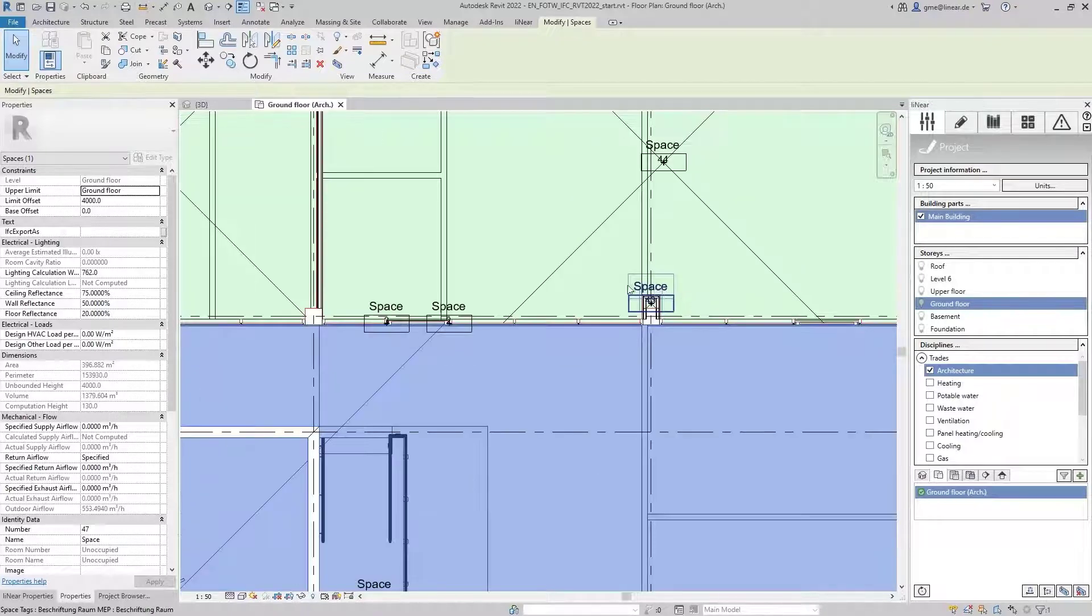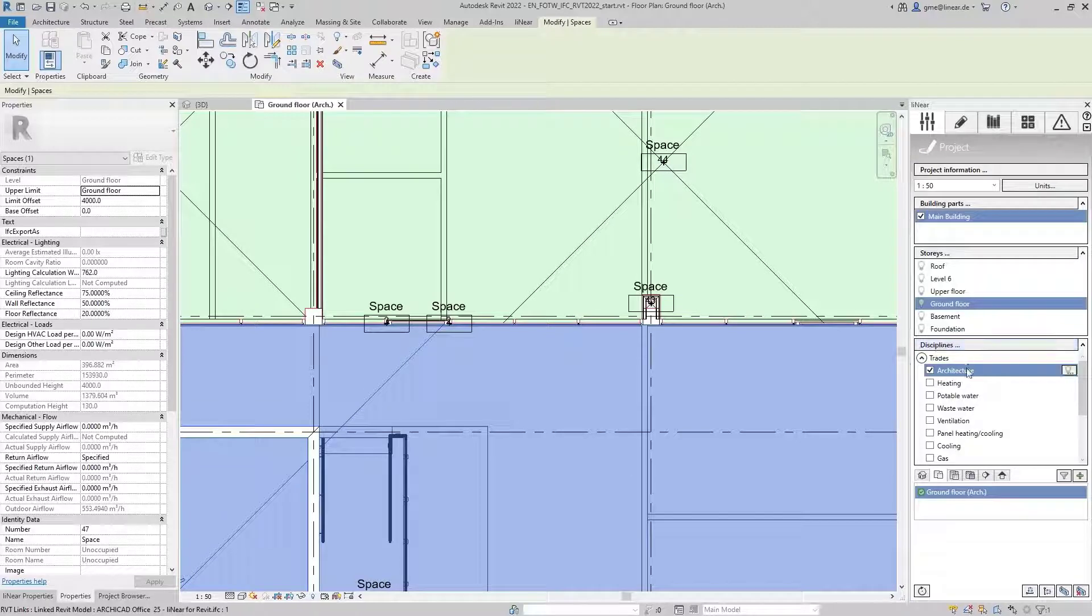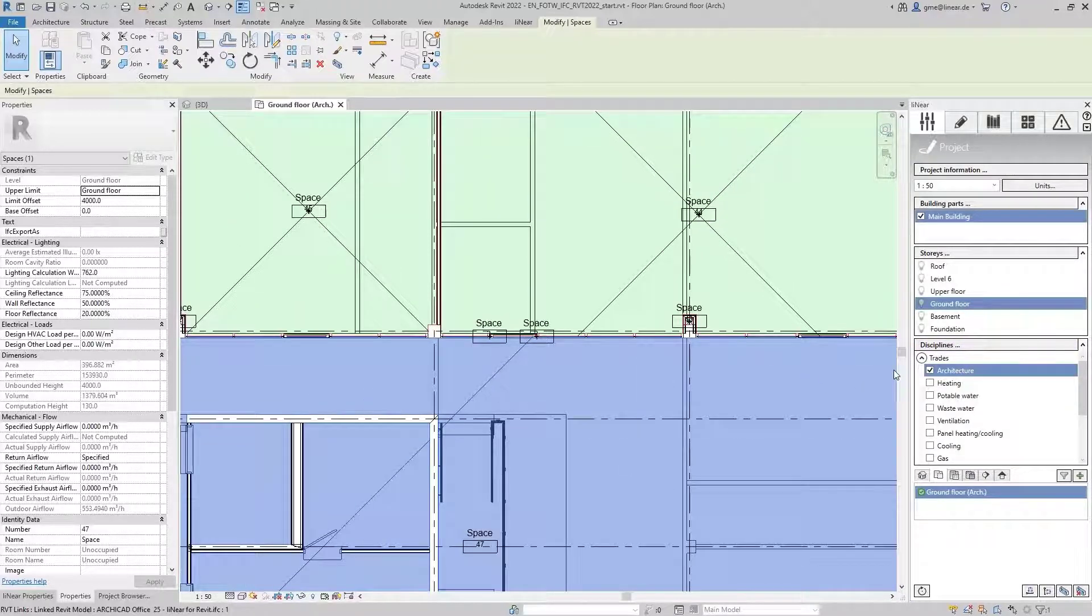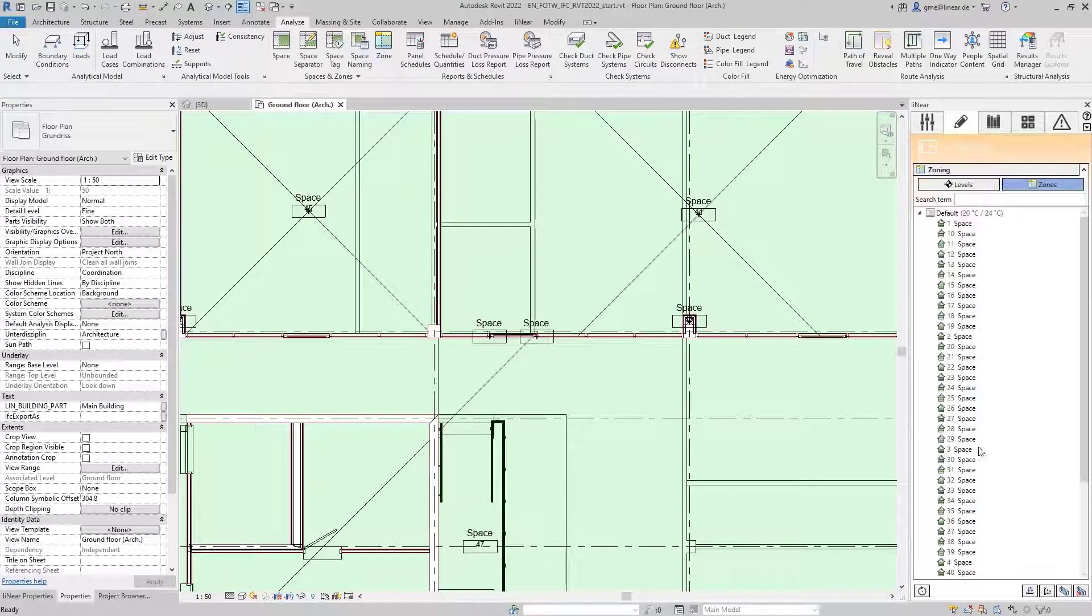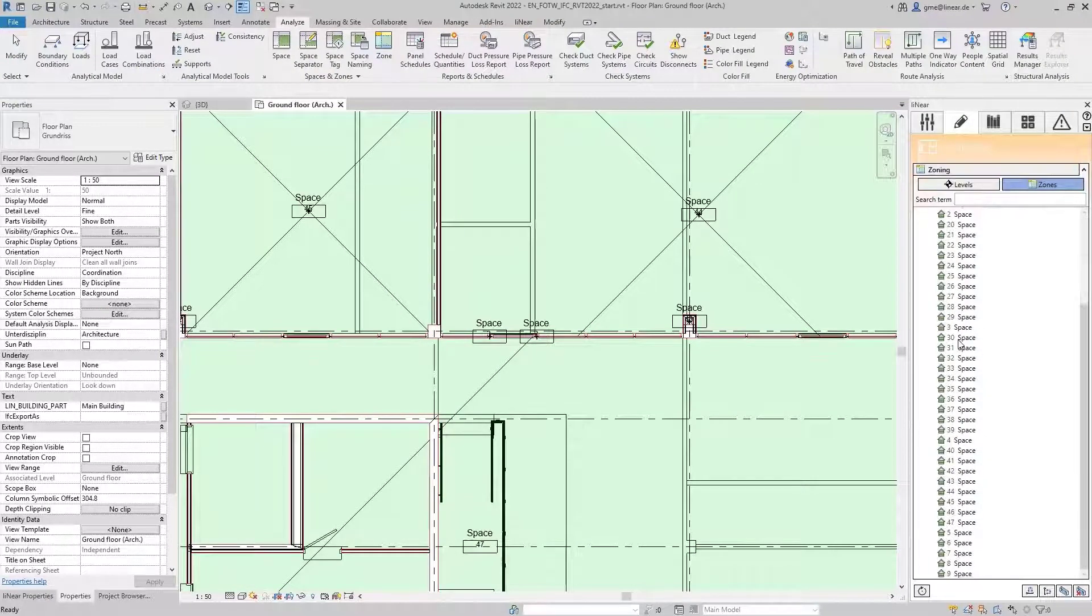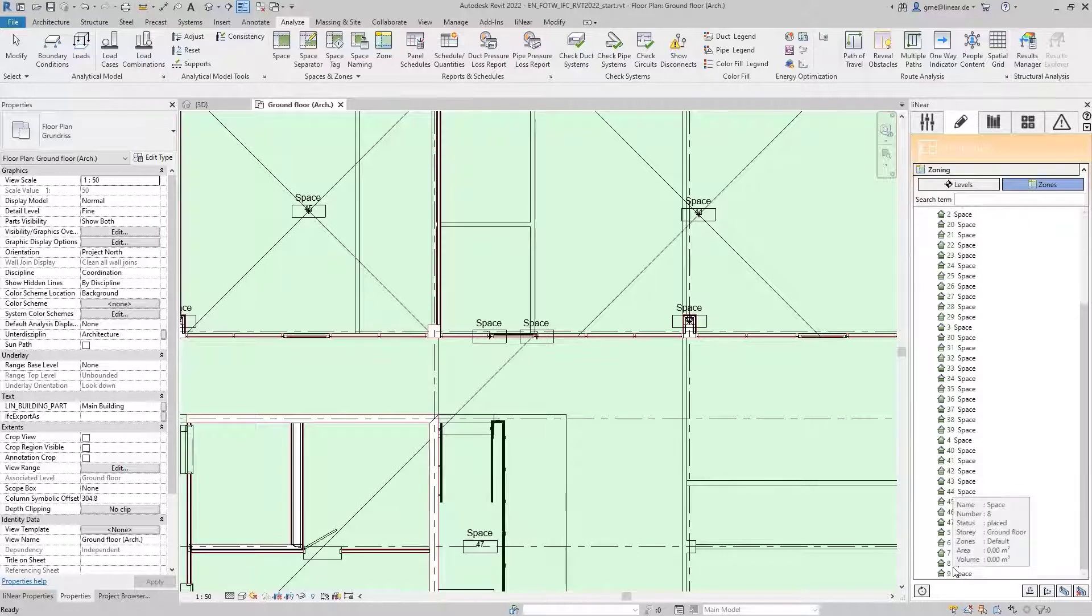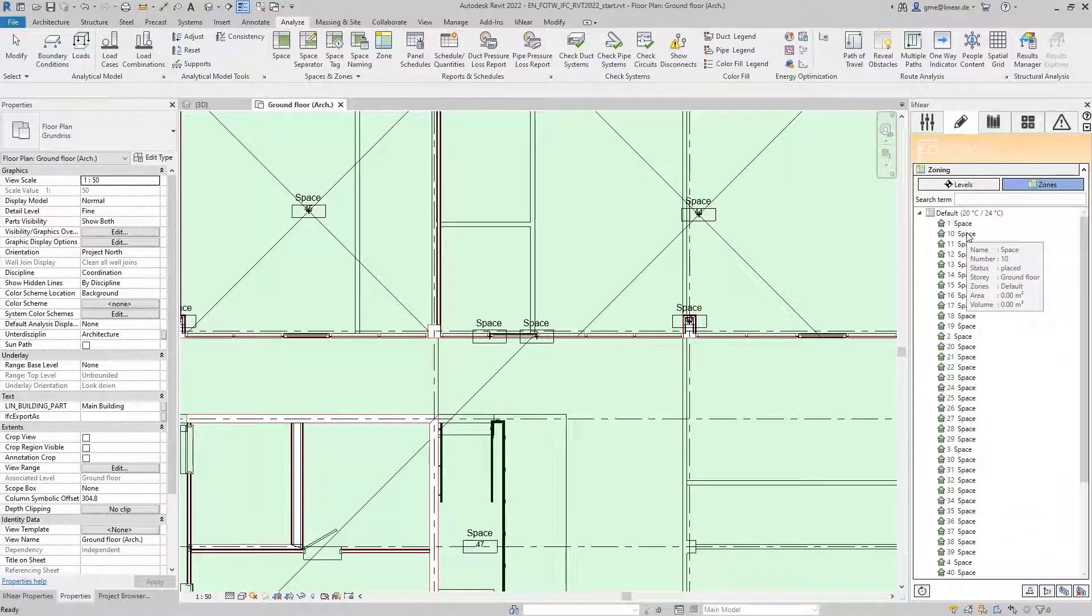A look at the text also reveals that room names and room numbers were not taken from the IFC. Also, the MEP space naming command cannot do the synchronization. In the zoning dialog, we see all recognized rooms, but as mentioned, we only get numbered MEP spaces, which now need some elaborate reworking.